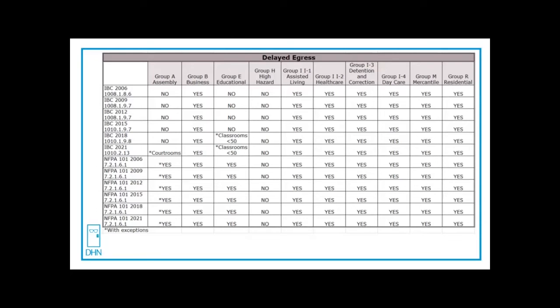Although in Group E educational, which is K through 12 and some daycares, starting in 2018, IBC classrooms that are less than 50, they do permit it on a secondary exit from that space, as long as it's not the main entry. NFPA 101 does allow it in Group E educational.